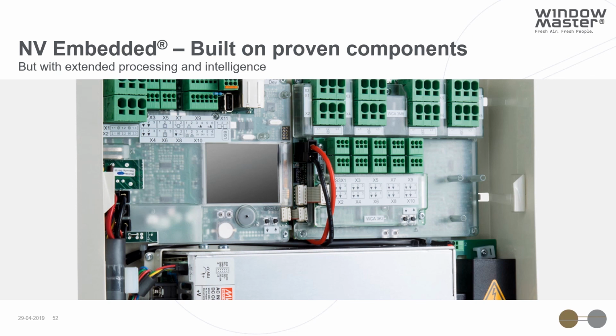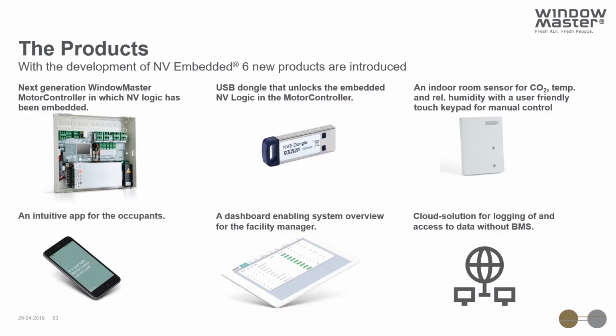NV Embedded is built on proven components. It uses a new generation of our motor-link controllers that's been well proven over the last 10 years or so. It uses a dongle to enable the onboard logic, but also to store zone information and naming criteria, as well as sharing information between different controllers. And we have a new indoor room sensor, which has CO2, temperature and humidity capabilities, as well as an override keypad for that zone.